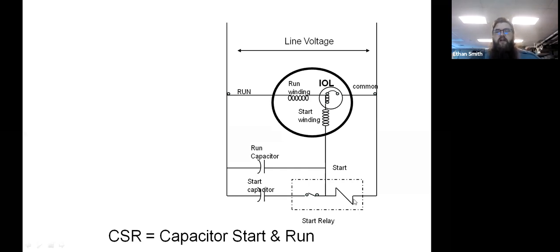So this relay will drop out, in a typical compressor situation, somewhere between 370 and 350 volts usually. It will disengage, and these are normally closed relays. And so when it energizes that coil, it actually opens this up and breaks the circuit to that start capacitor, takes it out of circuit. So what this does is it gives us that extra phase shift with that start capacitor to give us a little extra starting torque on these high load motors. But once that starts, we don't want it to keep running that start capacitor, because that start capacitor is usually enormous and it's not rated for continuous use.